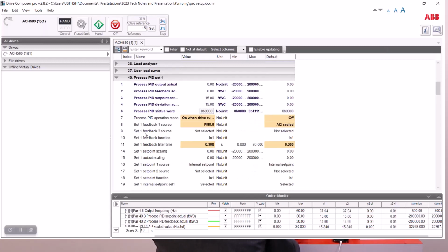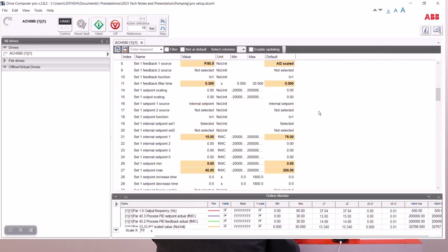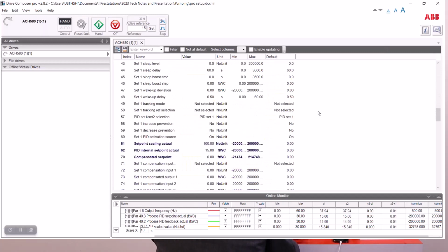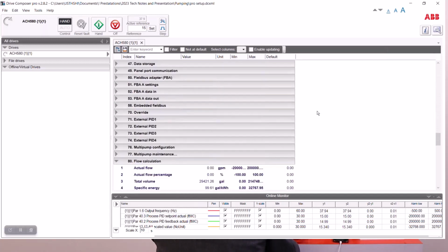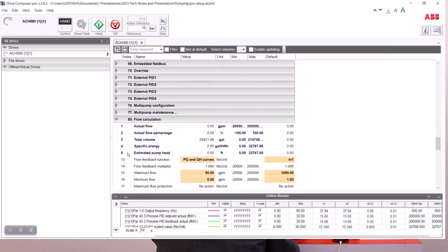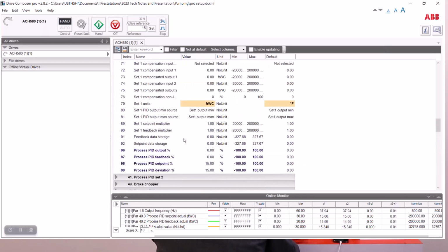And the PID loop I have set to on when the drive is running. Set 1 feedback 1 source is parameter 80.05. Let's slide down to parameter 80.05 so I can show you what that is. Parameter 80.05 is the estimated pump head being done in the flow calculation section. So back up to the PID loop area.